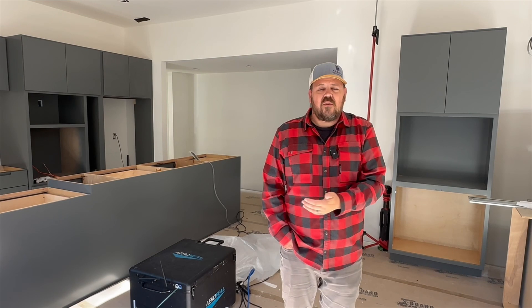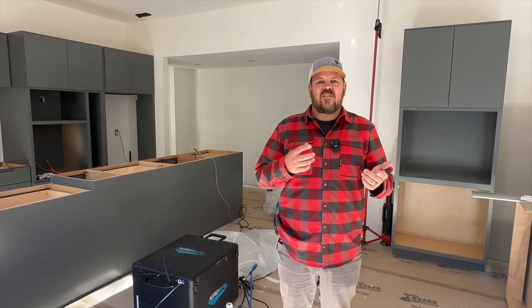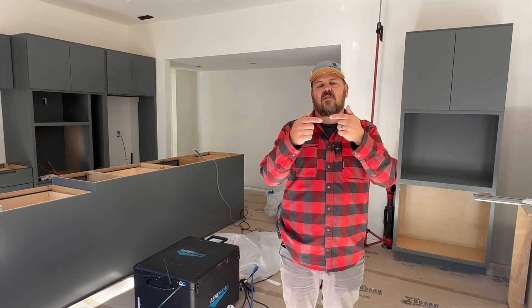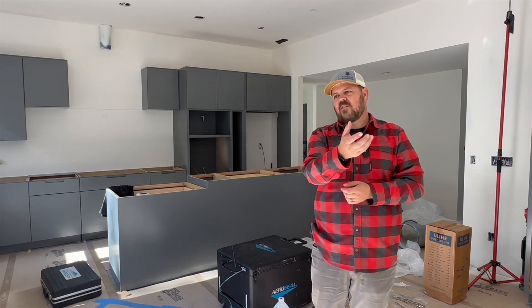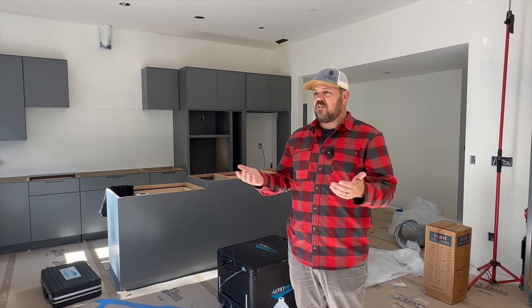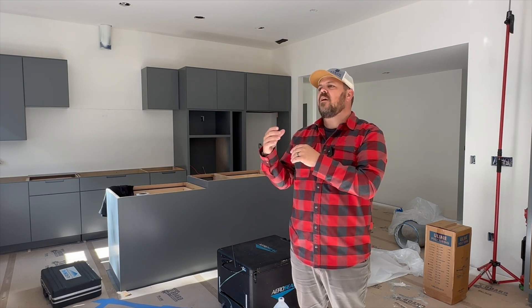In this house we have low ceilings and not much space — it's really a mechanical closet, smaller than my coat closet at home. The only option we had was for the ductwork to go up, across, and back down and in. We took the six inch duct to the top side of the trusses and back down, so we have roughly 20 inches of insulation on top of it. We're not too worried about temperature loss since the ductwork is sleeved with R5 insulation and also buried in insulation.